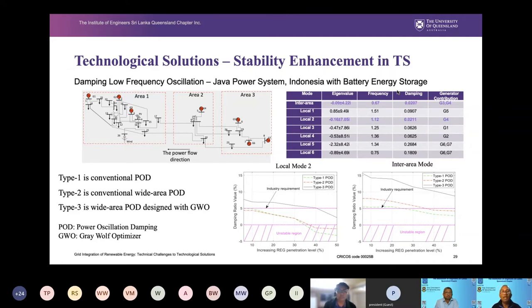In the inter-area mode, two groups of generators, far apart in two geographical areas, oscillate against each other and then create problems. After some time, the system gets into trouble. The other problem is not as severe as the inter-area mode; it is a local problem. So in that particular system, we identified two problematic modes: one is a local mode, the other is an inter-area mode.